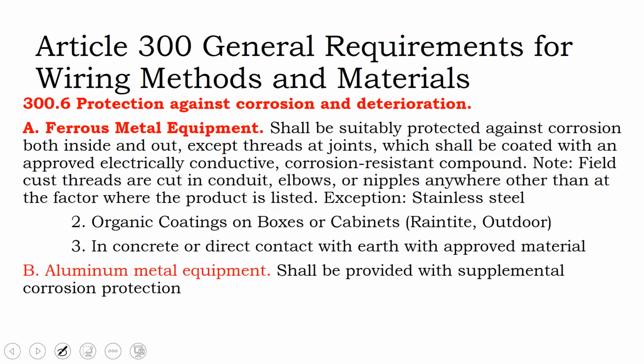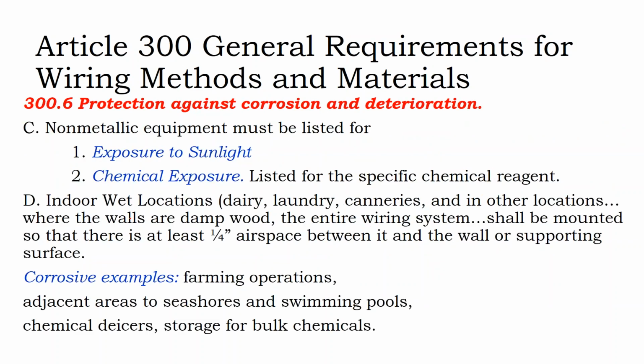Ferrous metal equipment shall be suitably protected against corrosion on the inside and out. So there's a requirement here for our metal boxes to be painted or galvanized, covered in an insulating material to resist corrosion. And that means we can't just butt metal up on metal and assume that it's going to be continuous, because the same way you protect against corrosion, you reduce your electrical conductivity as well.